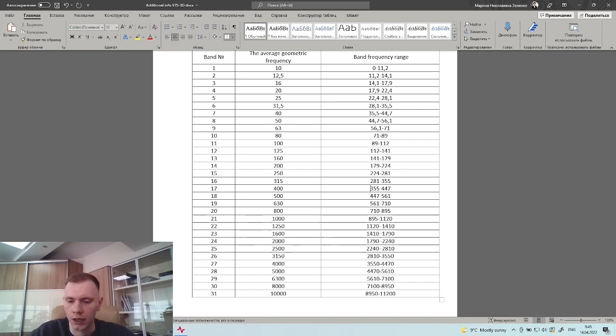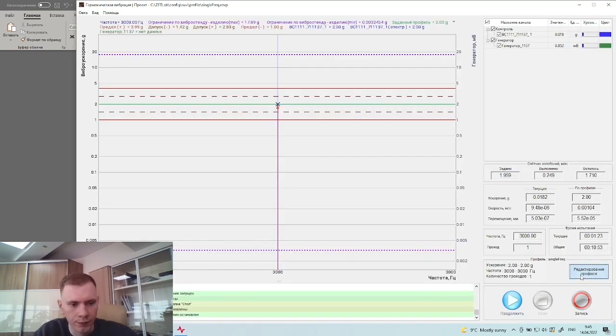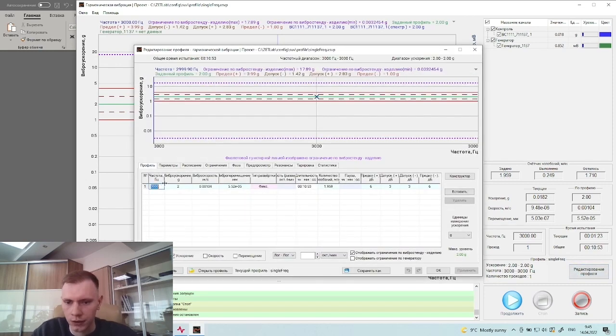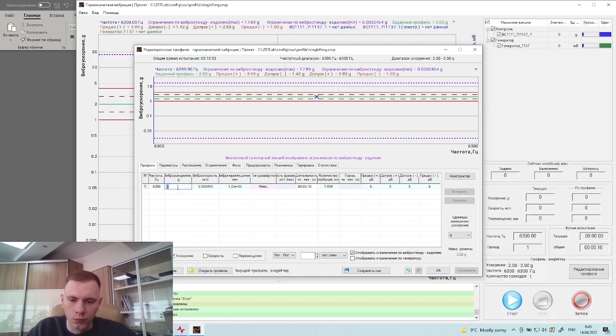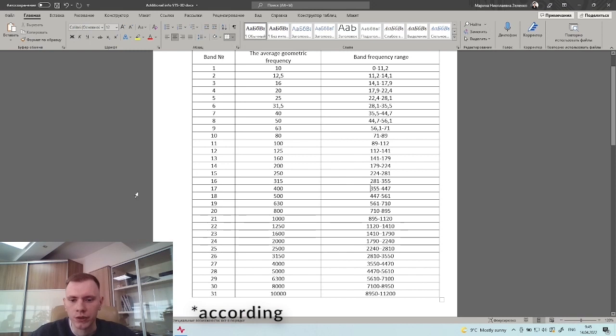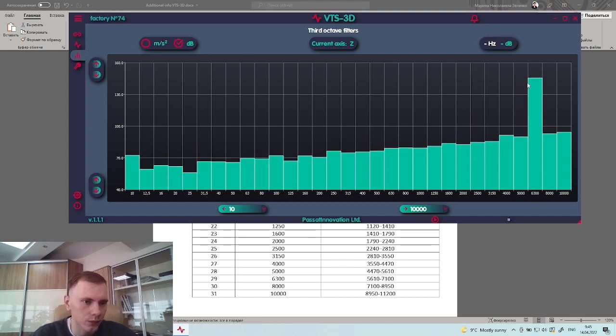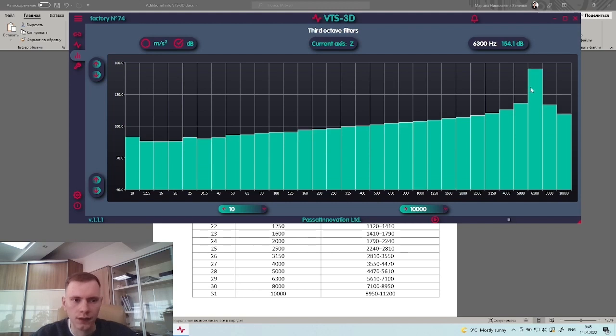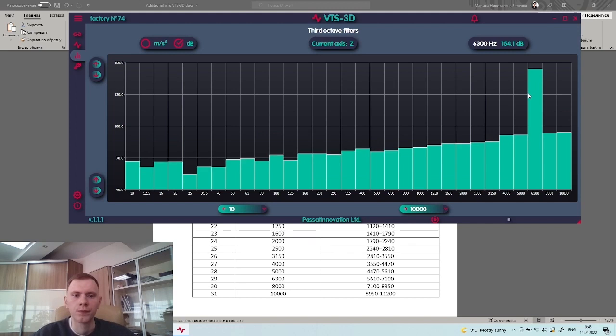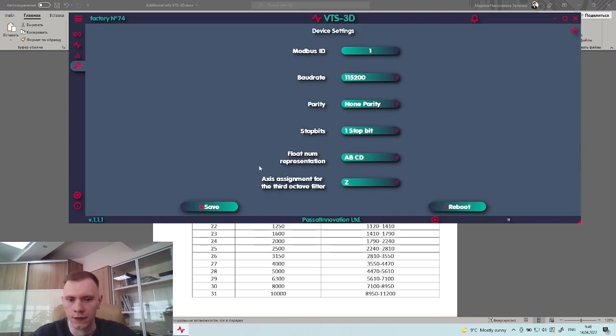So right now I will put some high frequency signal on our vibration exciter. Let's say 6.3 kilohertz. And we can put like 10G. And compared to this document, 6.3 kilohertz frequency is the average geometric frequency for this band. And here we can see that in this band we have the highest level of vibration RMS. I forgot to say that in these columns we have RMS of acceleration for one axis. You can change this axis in settings.